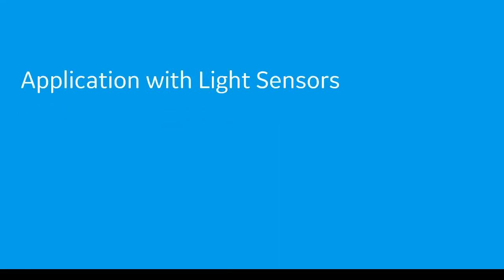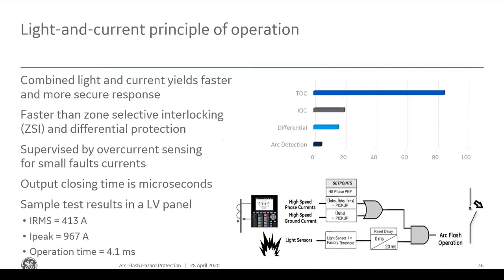Some of the applications with light sensors. We're getting pretty close to the end of the presentation here, the 1 hour. So I'm a little bit behind, but basically what the light sensor does is it detects light within the switchgear caused by the arc flash. Arc light is very fast, so we can detect light very fast, in less than a millisecond.